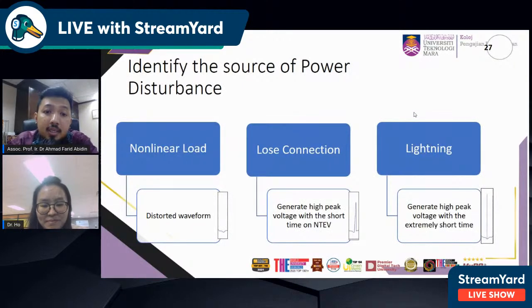Okay, when we identify there is an appearance of high neutral to ground or high neutral to earth voltage, from that kind of anomalies or disturbance, we are going to segregate or divide the disturbance in terms of three different causes: non-linear loads, loose connection, and lightning.